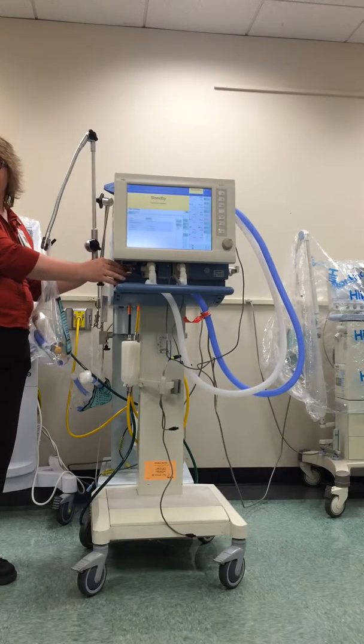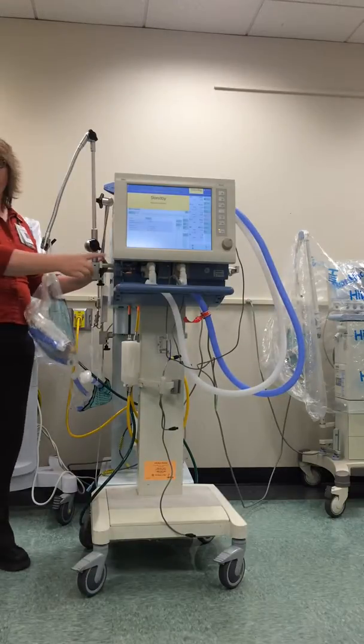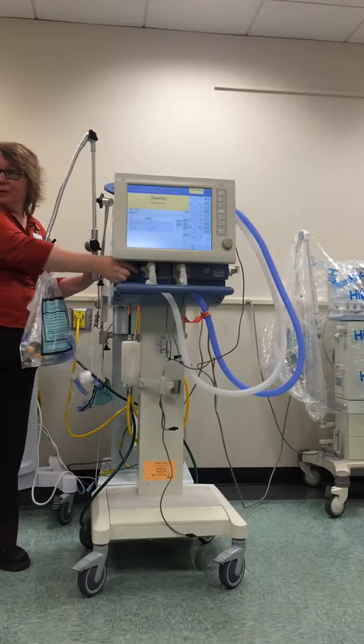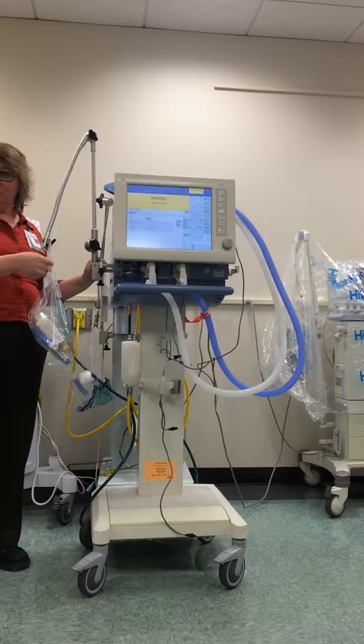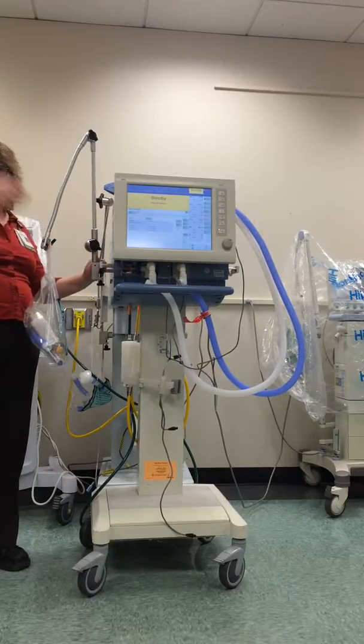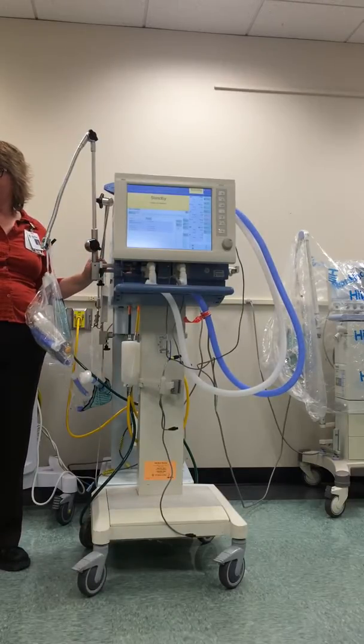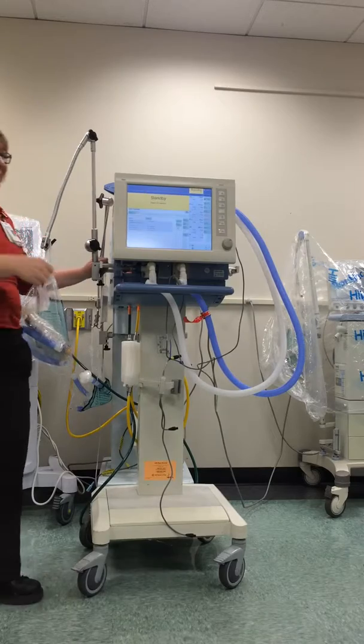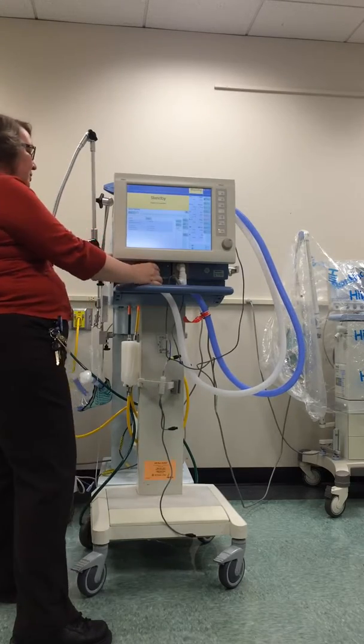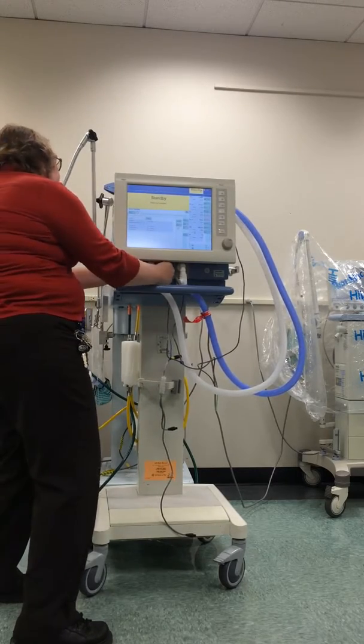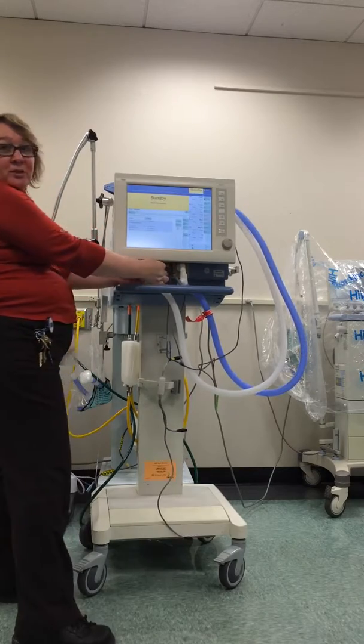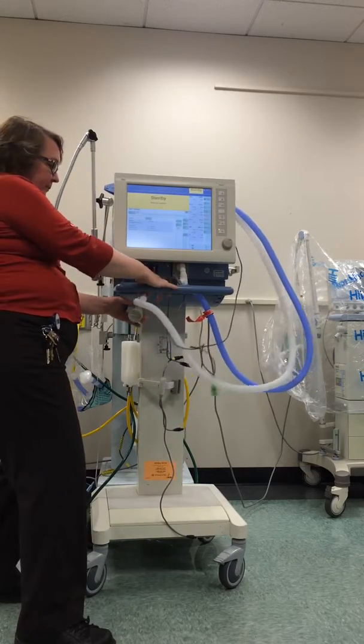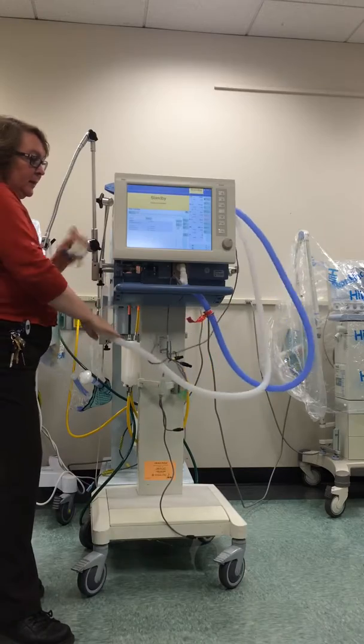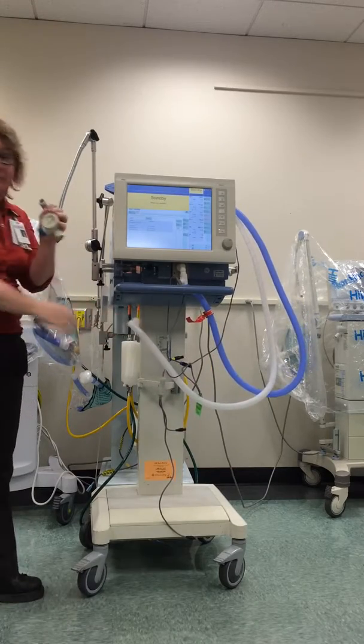But I'm going to show you the exhalation valve, so to that note, before you take the exhalation valve out, you have to slide the flow sensor out. Because if you don't, you take the exhalation valve out and the flow sensor flies across the room. It does, because I've done it before, because I forget. So there's a little blue tab in here that you have to push. And when you push that, then your exhalation valve will come out. And that's this piece right here.